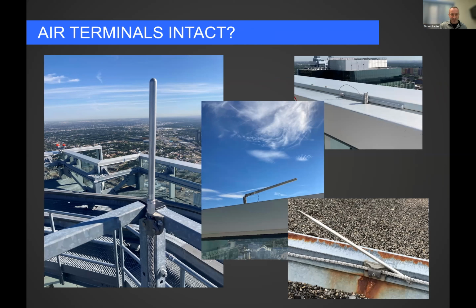It is absolutely intact. It's on top of a cooling tower. This is an example of a dead-ended air terminal because it dead ends down to the bottom of the railing where the main loop conductor is, and it bonds into that. From that point it has two paths to ground, which every air terminal has to have. That's looking good, and you can see the intact air terminals beyond it on the other side around that perimeter.